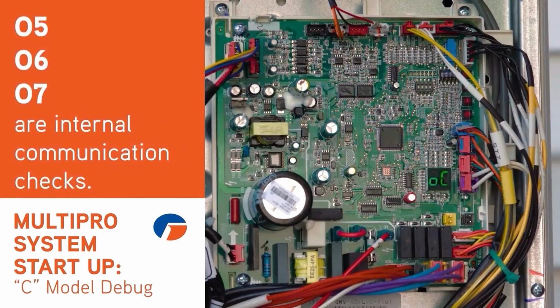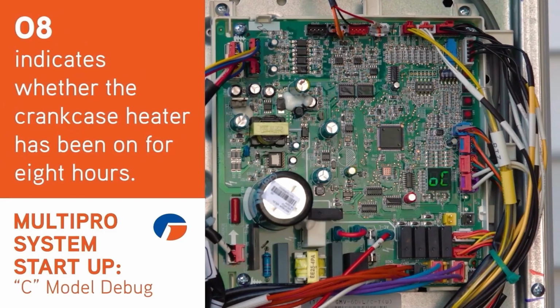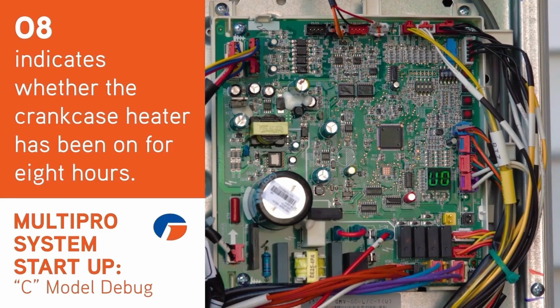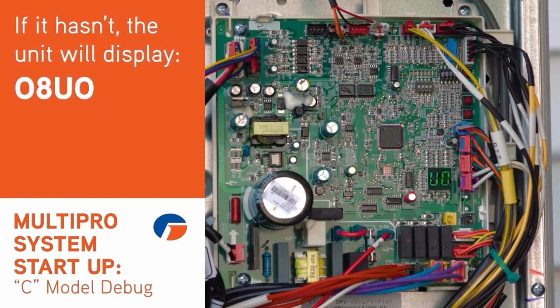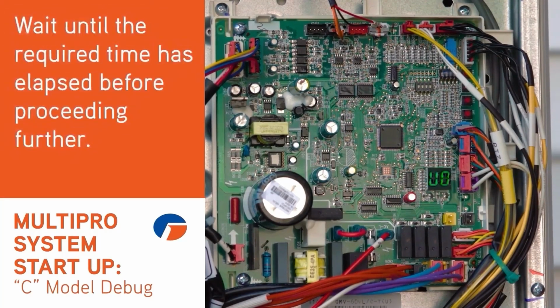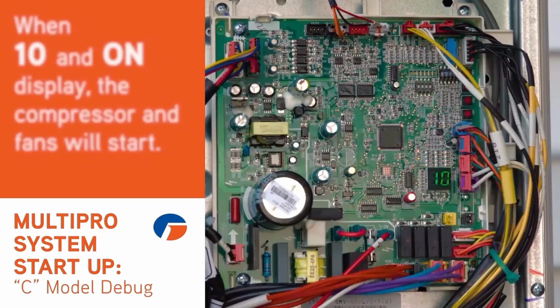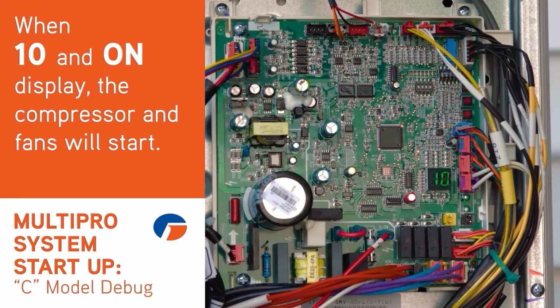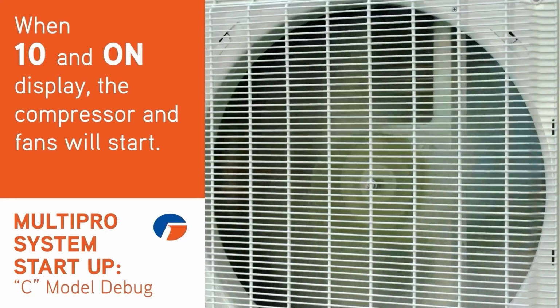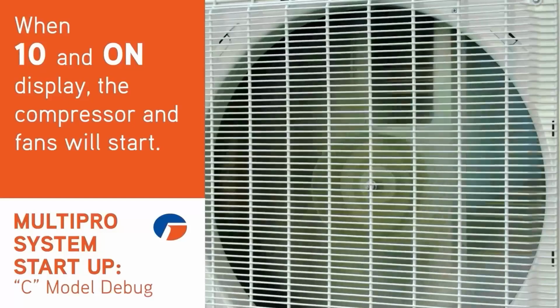05, 06, and 07 are internal communications checks. You'll do nothing. 08 indicates whether or not the crankcase heater has been on for 8 hours. If it hasn't, the unit will display 08 and then UO. You should wait until the minimum time has elapsed. If the power was on for 8 hours, the display will move on automatically. When 10 and on is displayed, the fan or fans and compressor will start. The system is checking that the service valves are open.